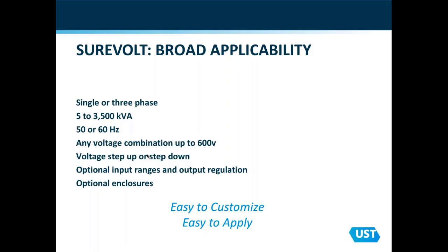Another nice feature is that we can step up or step down the voltage. So for instance, if you bought a machine from Europe and it ran on 400 volts, but your factory is 480, well, we can supply a product that will make that step from 480 to 400, and will give you 400 regulated voltage to plus or minus 3%. So it eliminates the potential need for an independent step-down transformer.